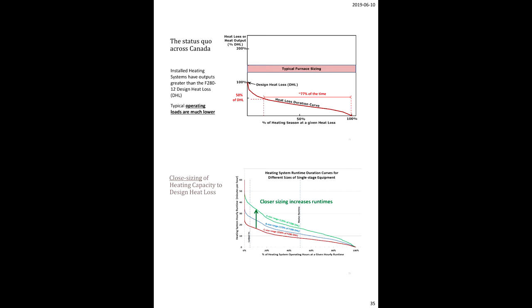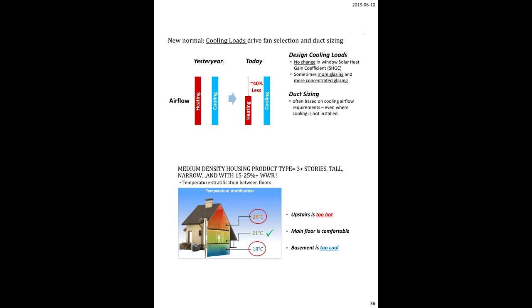Low loads are weird, because you have to adjust to people's comfort and make sure it balances the home. Cooling loads, yesteryear, we used to require cold air to have more CFM, right? 300 to 400 CFM per ton is about what we need on average, though every system differs a little. Then you need about half of that for hot air, because cold air is cold and heavy, so it's more dense. So the cooling loads were smaller, heating loads were higher, but it meant the ductwork leveled out at about the same size.